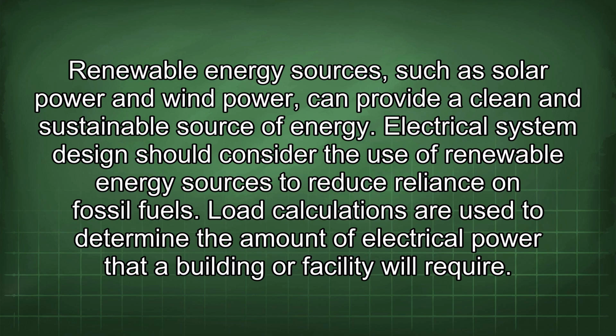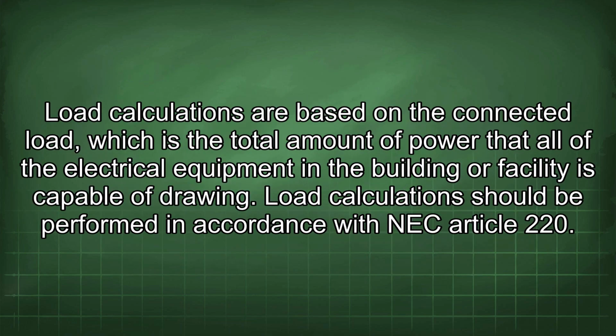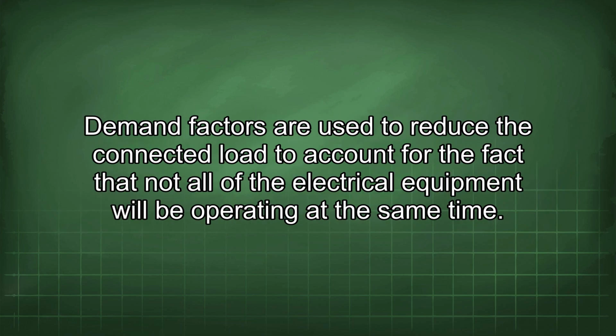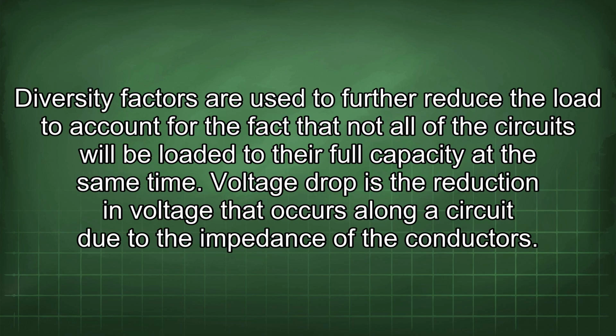Load calculations are used to determine the amount of electrical power that a building or facility will require. Load calculations are based on the connected load, which is the total amount of power that all of the electrical equipment in the building or facility is capable of drawing. Those calculations should be performed in accordance with NEC Article 220. Demand factors are used to reduce the connected load to account for the fact that not all of the electrical equipment will be operating at the same time. Diversity factors are used to further reduce the load to account for the fact that not all of the circuits will be loaded to their full capacity at the same time.